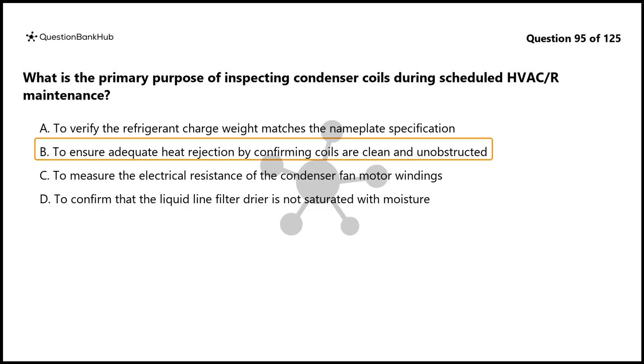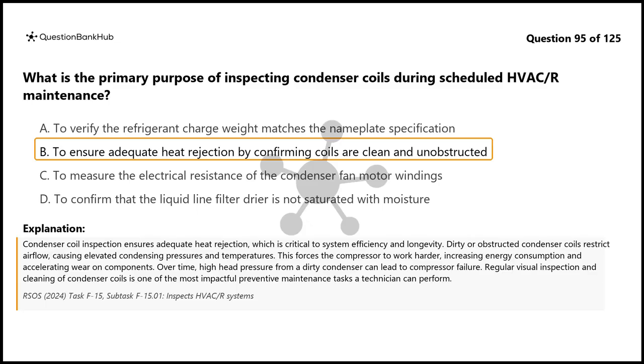The correct answer is B. Condenser coil inspection ensures adequate heat rejection, which is critical to system efficiency and longevity. Dirty or obstructed condenser coils restrict airflow, causing elevated condensing pressures and temperatures. This forces the compressor to work harder, increasing energy consumption and accelerating wear on components. Over time, high head pressure from a dirty condenser can lead to compressor failure. Regular visual inspection and cleaning of condenser coils is one of the most impactful preventive maintenance tasks a technician can perform.